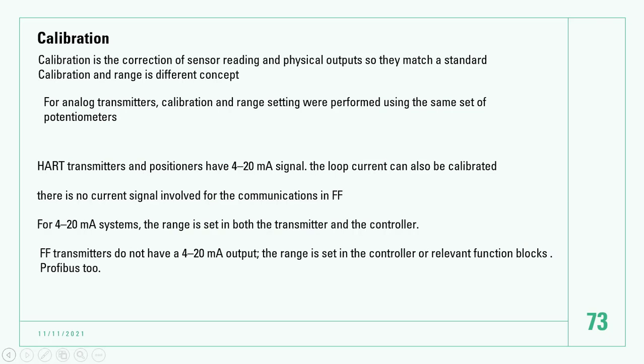Calibration. What does calibration mean? Calibration is the correction of sensor readings and physical outputs. So matching a standard, calibration and range are different concepts. This is a serious concept. Actually, calibration is just about the sensor: the physical signal should match the electrical signal. That's it. Okay, this is for an analog transmitter.